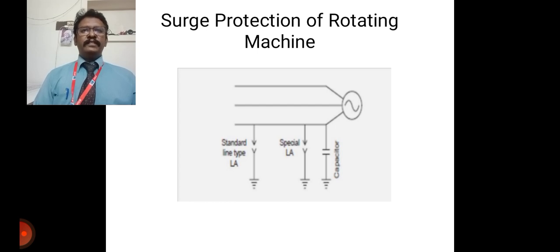This means that in case of surges with a steep front, the voltage will be concentrated at the first few turns. Since the insulation is not immersed in oil, its impulse ratio is approximately unity, whereas that of the transformer is more than 2. These points you have to keep in mind. The rotating machine should be safeguarded against major and minor insulation failures. By major insulation, we mean the insulation between winding and the frame, and minor insulation means interturn insulation. These differences you have to keep in mind.